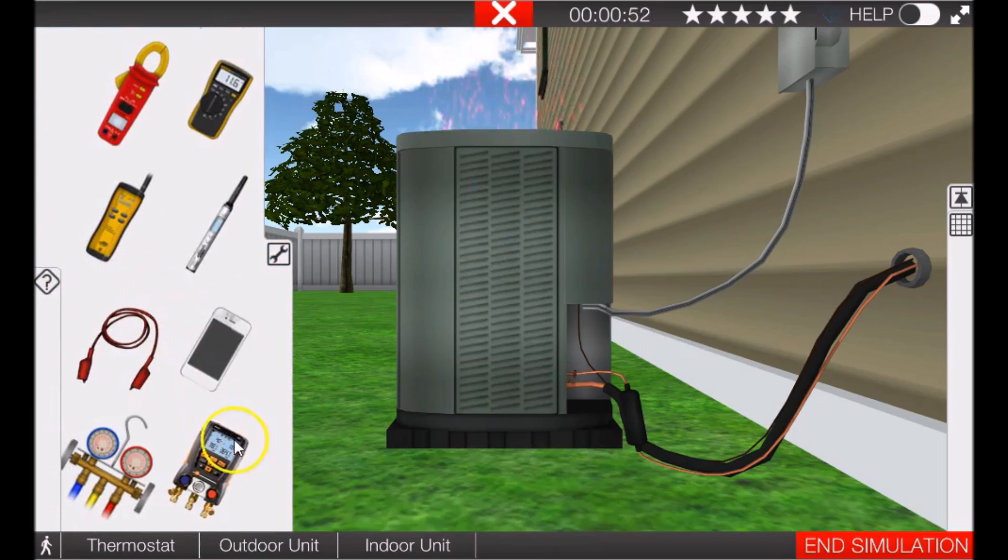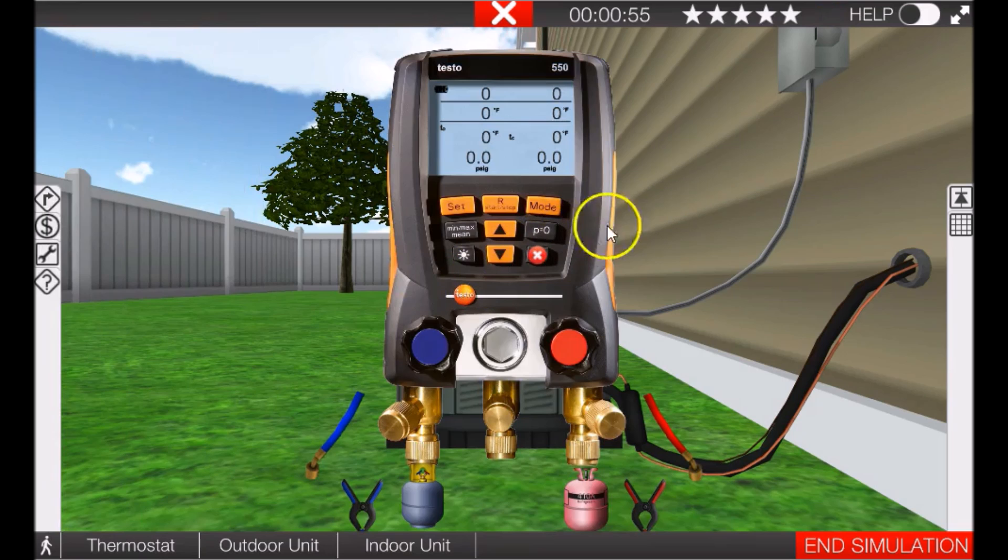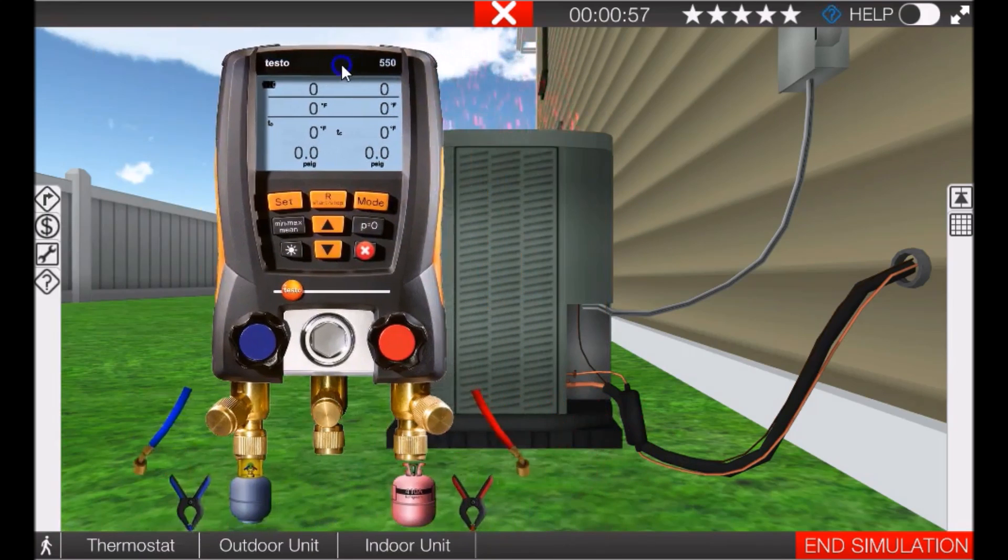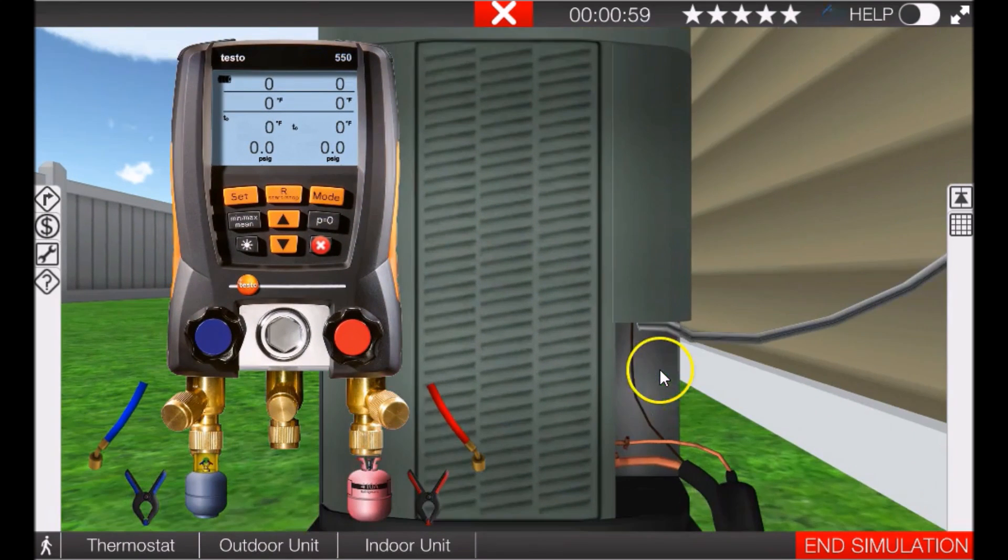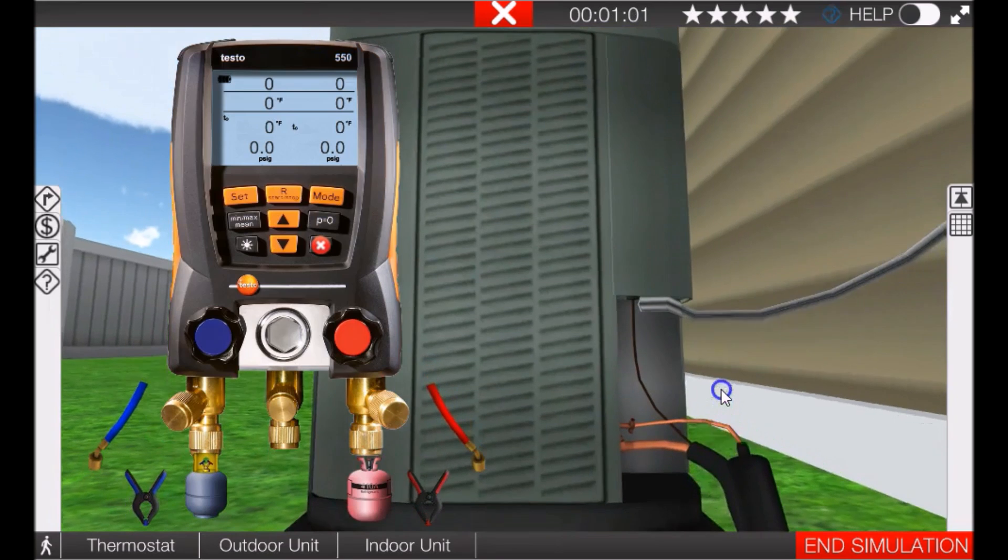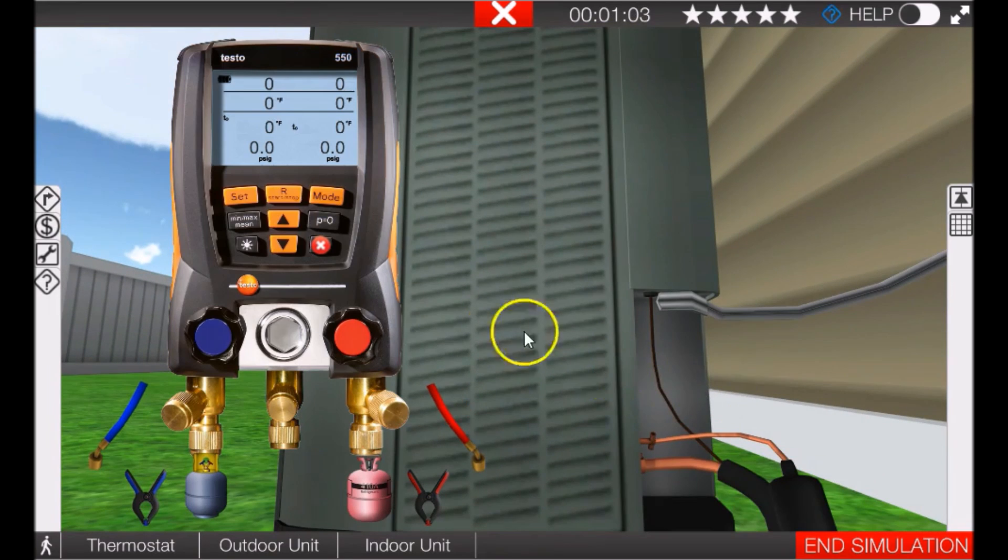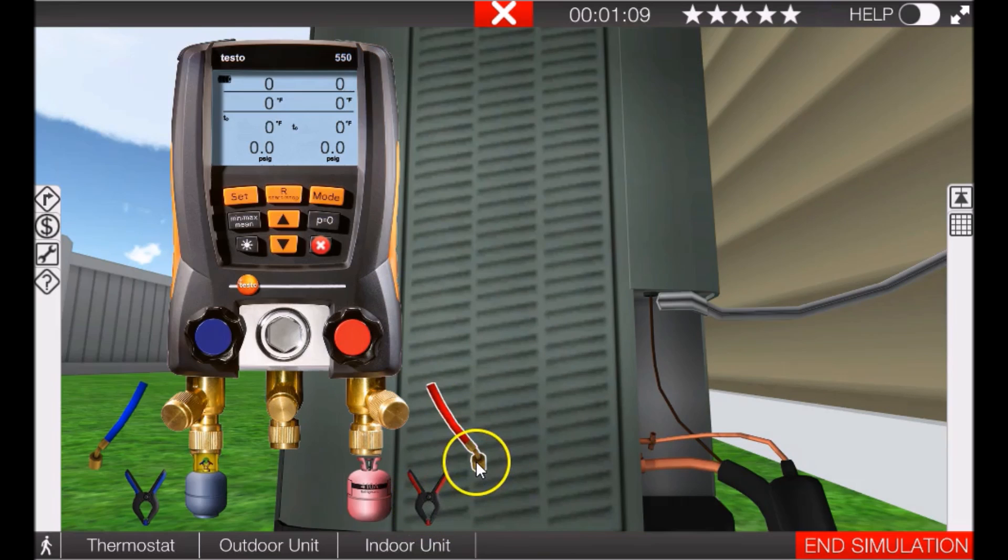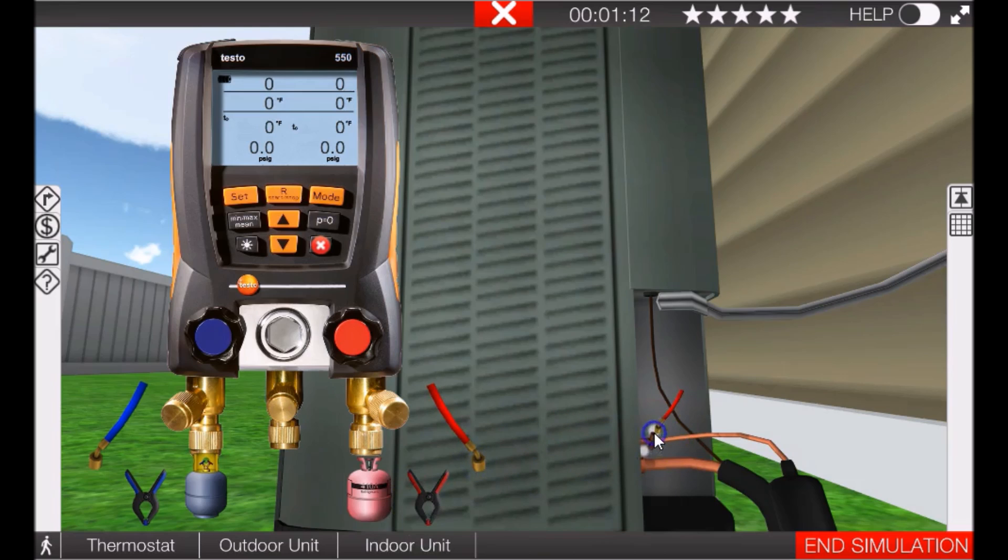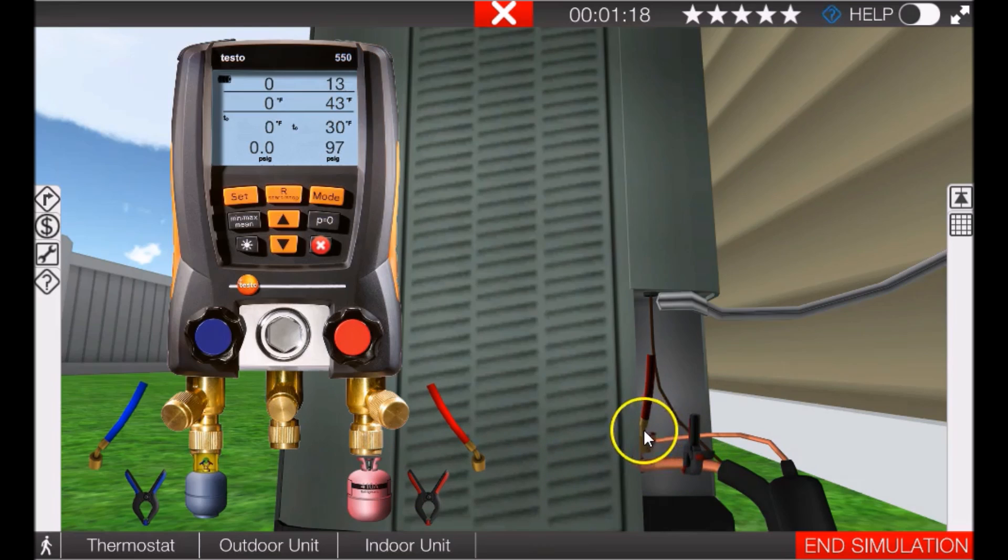We'll use our Testo gauges because it's easier to see. Move them out of the way a little bit, zoom in here on the discharge and suction lines. Okay, so here's our red hose, high side hose, and here's our high side temperature clamp, so we'll put those on the discharge line.